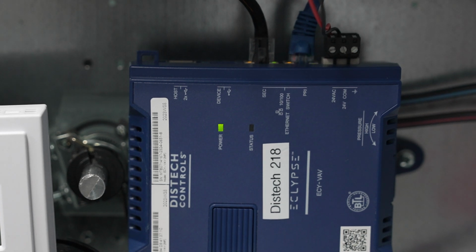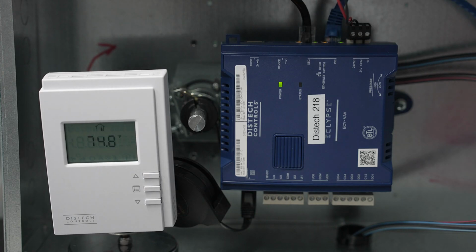controller, are on. If you'll be using the thermostat to set correction factors and record initial values of the unit, you will also need to confirm communication and proper operation of the thermostat during this time. Otherwise, you will need to be able to interface with the controller through its IP address and access the controller software to make your adjustments.